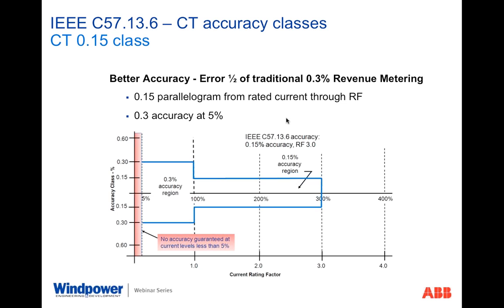When you go below 100% down into the 5% of current range, it can degrade down to a 0.3 class, or 1/2 of what the original 0.3 classification was. In other words, it was 0.6 down at that end on the 0.3 class. Here it's 0.3 error on the 0.15 class. So everything is cut in half in terms of the error values. And what's more important, we're starting to see an expansion of that current measuring range all the way down to 5% of rated nominal current.